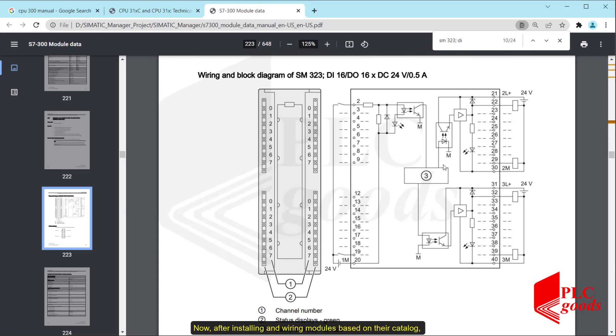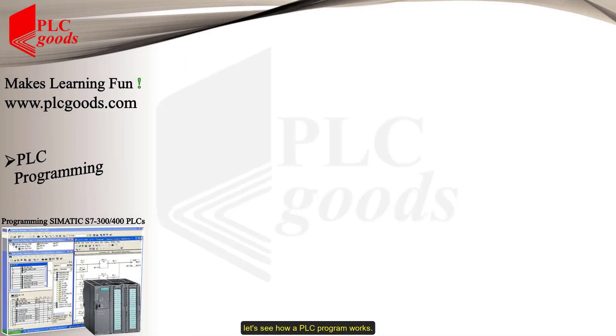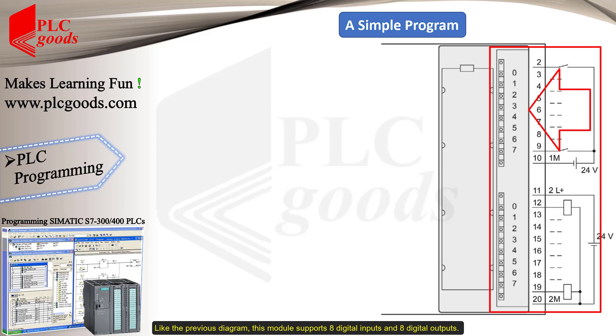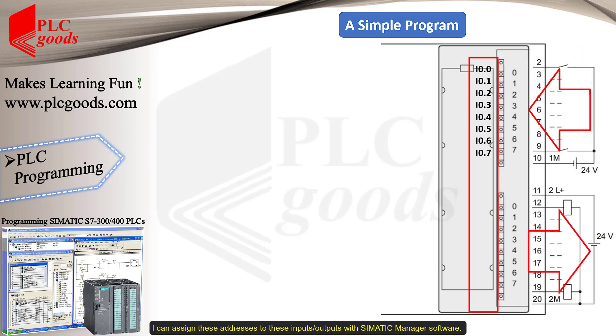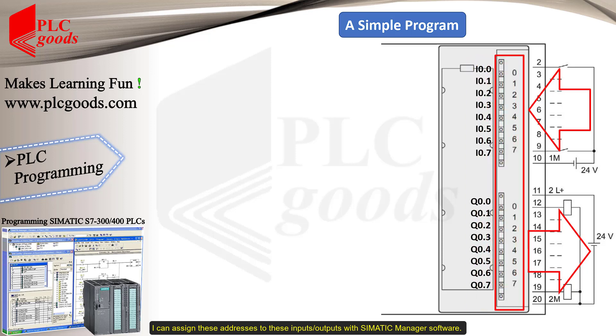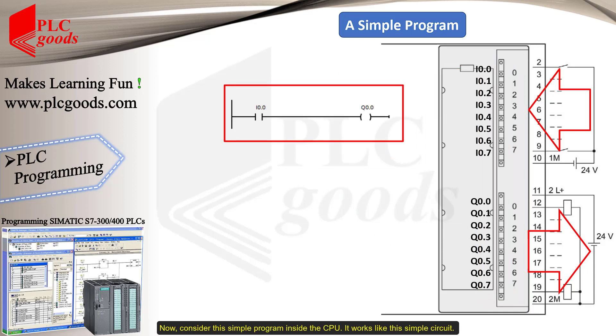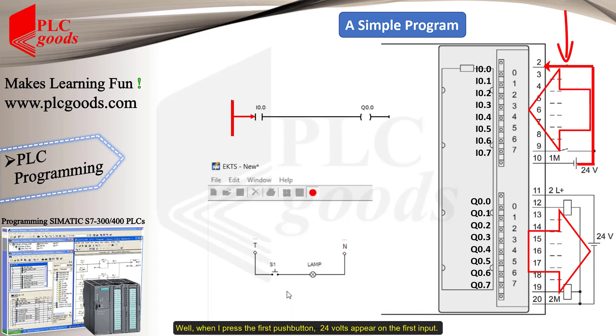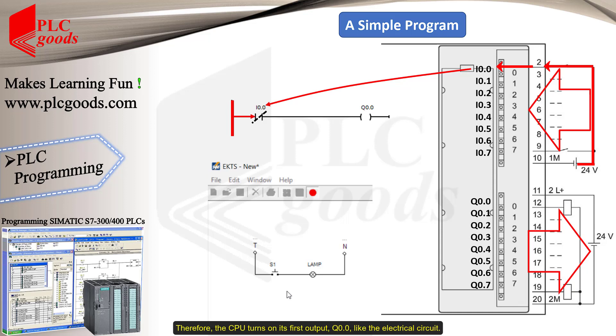Now, after installing and wiring modules based on the catalog, let's see how a PLC program works. This module supports eight digital inputs and eight digital outputs. I can assign these addresses to the inputs and outputs with SIMATIC Manager software. Consider this simple program inside the CPU — it works like a simple circuit. When I press the first push button, 24 volts appear on the first input, and its corresponding contact in the program, I0.0, changes to closed. Therefore, the CPU turns on its first output, Q0.0, just like an electrical circuit.